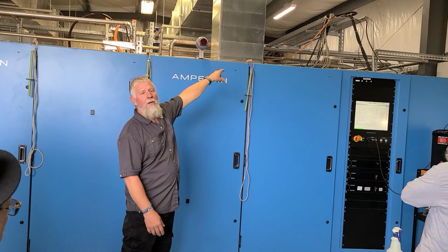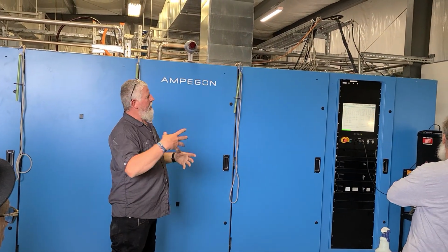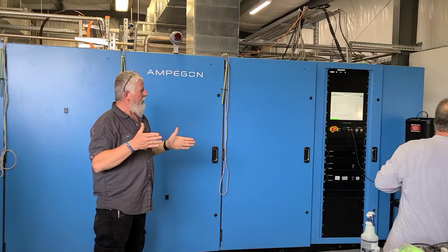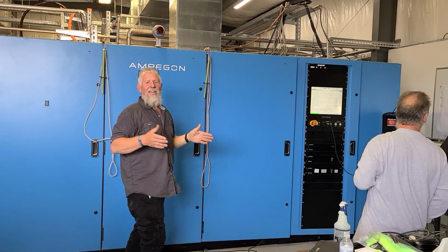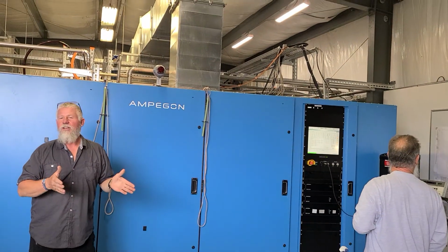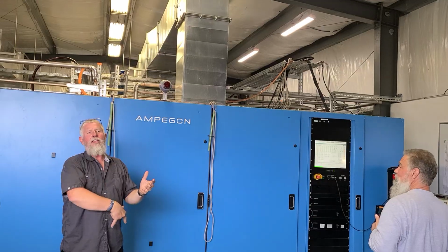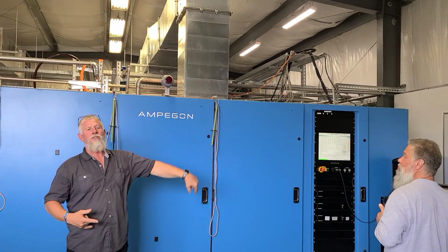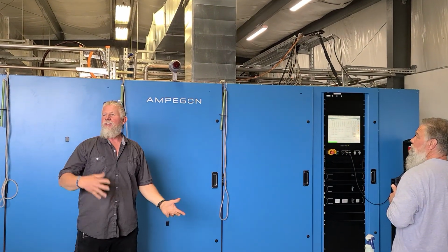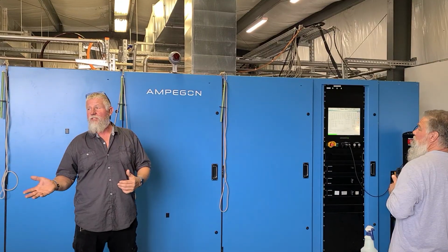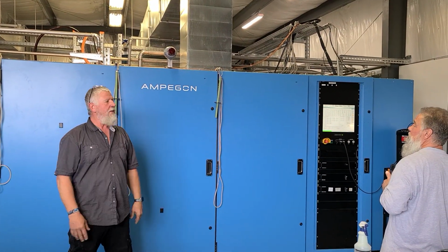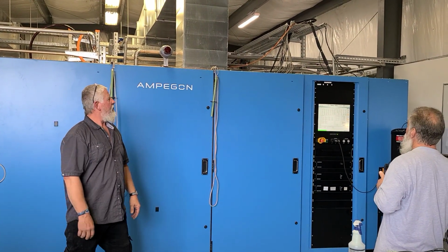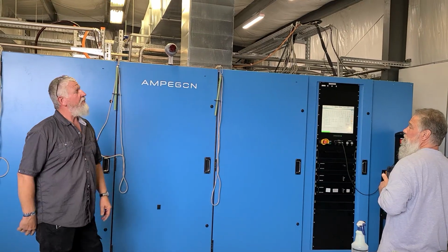The pump is on the back wall there, and then it has a heat exchanger, where it pumps the hot water into the heat exchanger, and the other side of it is cool water from the outside. It's just blowing, not chilled with refrigerant, just air blowing through it, and that brings it down to ambient outside temperature.